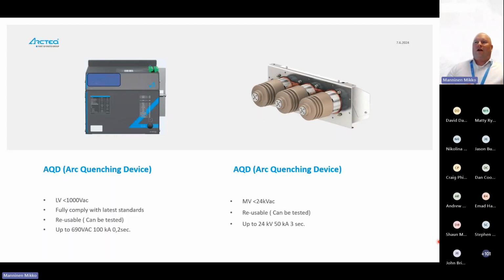Mentioned earlier already, arc quenching devices. There are different technologies. An arc quenching device makes a parallel path for the fault current to travel. In the standards, it is called arc transfer current, arc transfer. So from the arc fault, which has a changing impedance when the arc electrode is burning, it transfers to something which is controlled. Very, very low impedance, but it's controlled. It's more like a star point to the system. So these arc quenching units, no matter what brand, their main purpose is to absorb the energy.